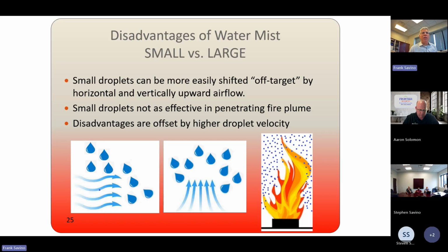Okay. So some additional disadvantages. By the way, Jeff is going to have to leave soon, so I'm going to be on my own after that. Thank you, Jeff, for that. So, some of the disadvantages: smaller droplets can more easily be shifted off target by horizontal and vertical upward airflow. So there are limitations in terms of horizontal airflow that you need to be attentive to with regard to water mist, as you also have to do with sprinklers.